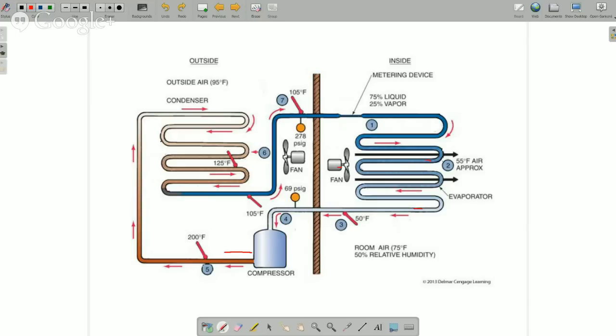So as it enters the condensing unit, it's going to change state from vapor to liquid. It's going to get rid of all of that heat. And what happens is it goes through this condenser just like it should, but instead of beginning to back up here, it backs up earlier on in the condensing unit. So this is now all liquid where it should be changing state.